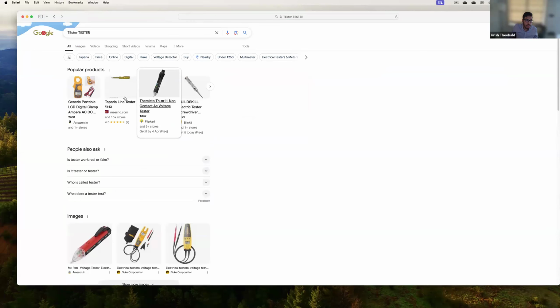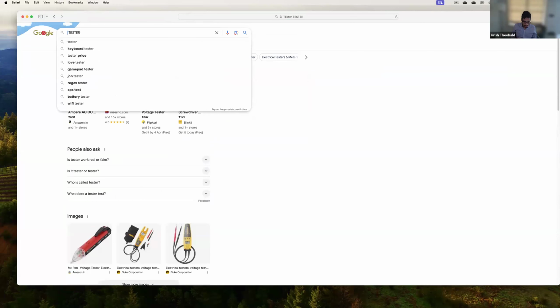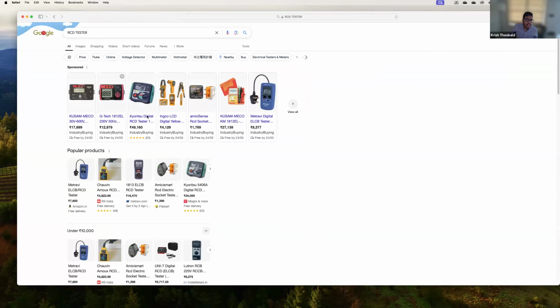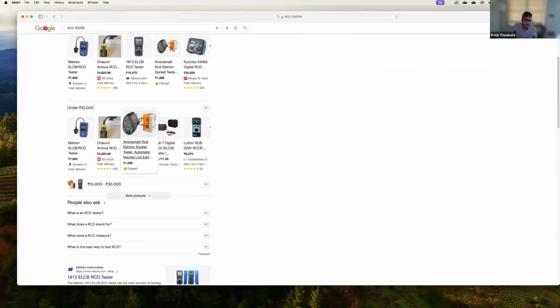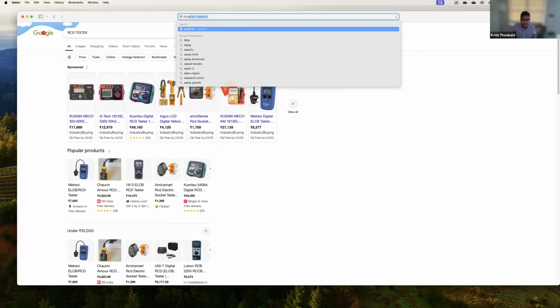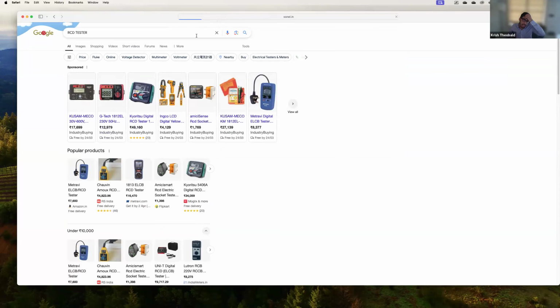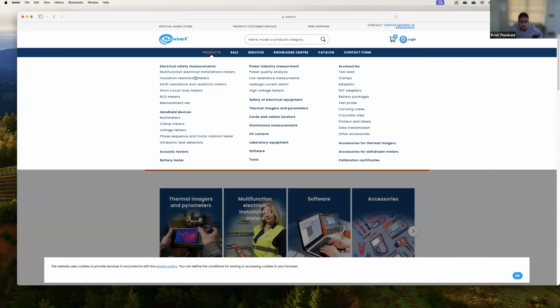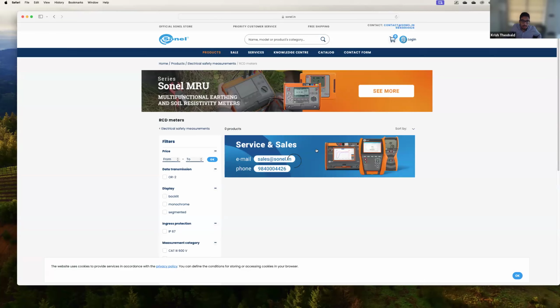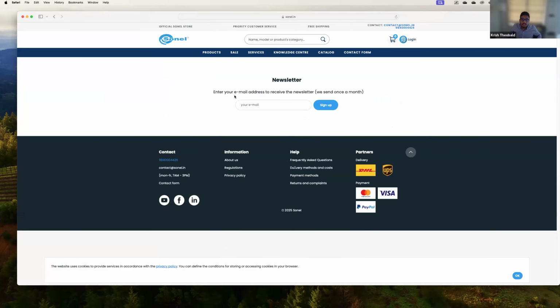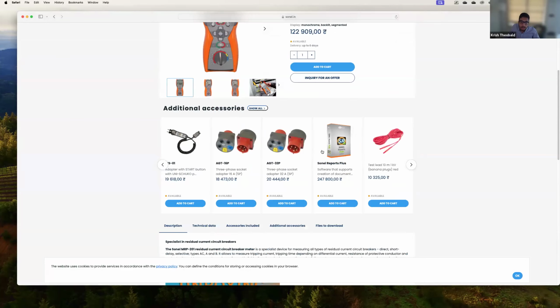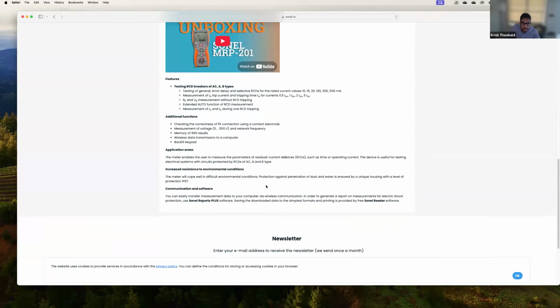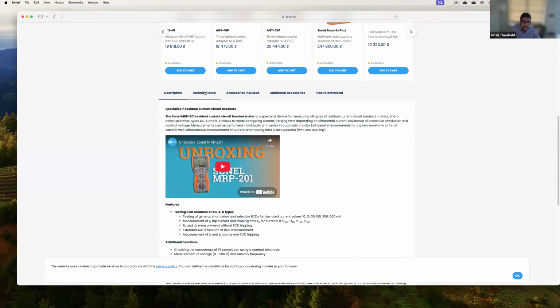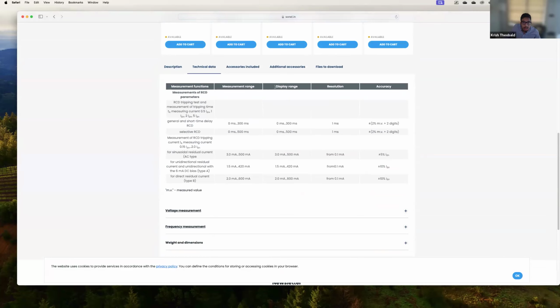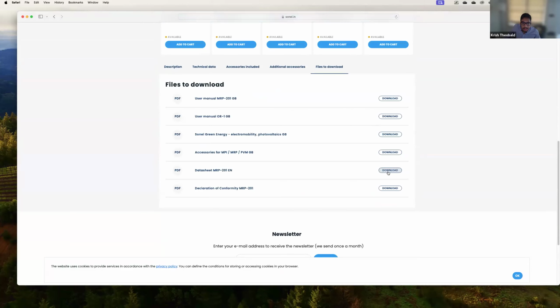don't go for all this small nonsense. Sorry, one more. RCD tester. A device like this, we don't know whether it actually conforms to the standard. You need to see. An example is there's a company in India called Sonel. They make an RCD tester that actually complies to the standard. See, RCD meters. And then you have here, this particular device, it actually conforms to that standard. It will be mentioned in the data sheet, technical data, files to download. Data sheet.